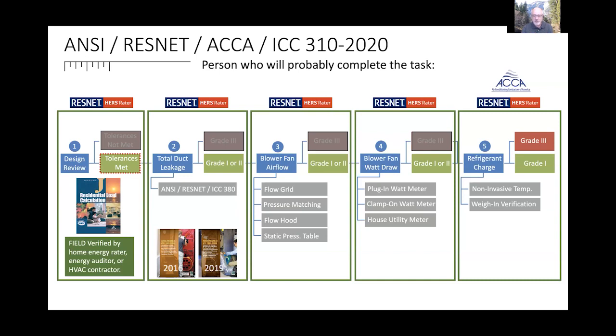Some people do their charge based upon superheat or subcool or some other requirement for the install for that manufacturer. That doesn't cut it in terms of what we're trying to do here for this verification. It's a weigh-in verification, so if they're able to do that, you can have your documentation ready ahead of time, as long as it's done and verified correctly. So there is some learning curve happening here.